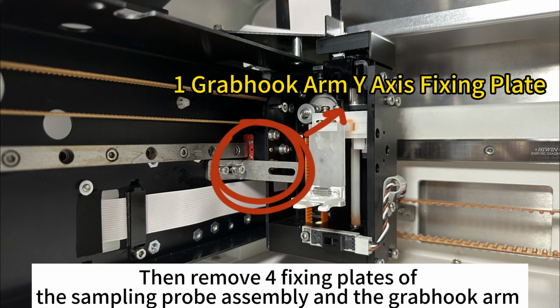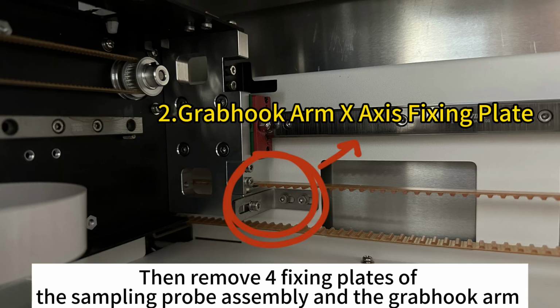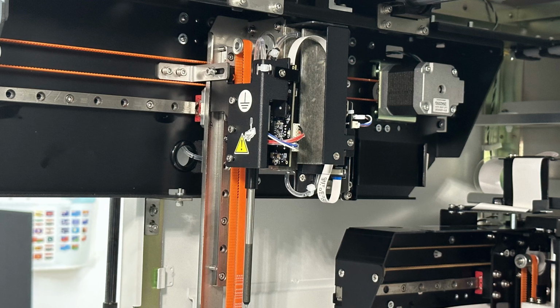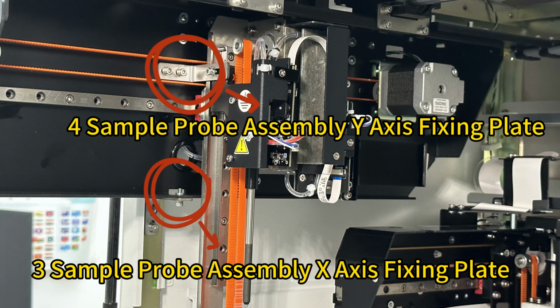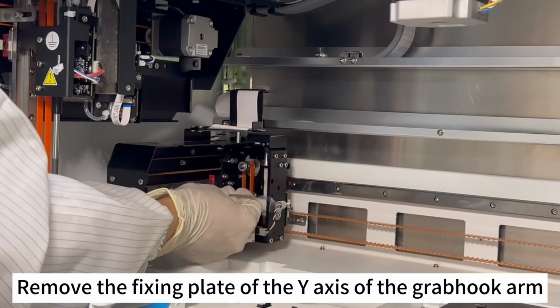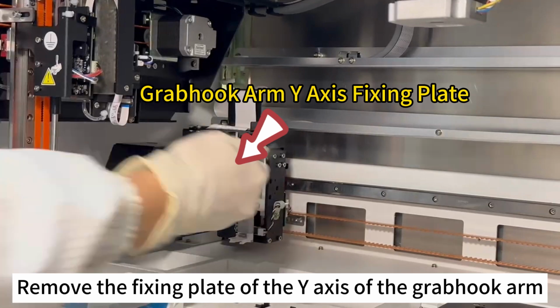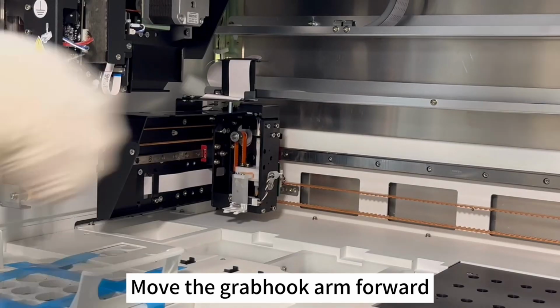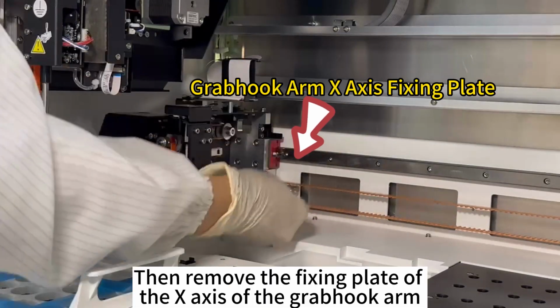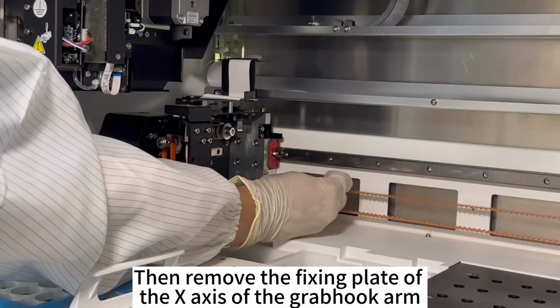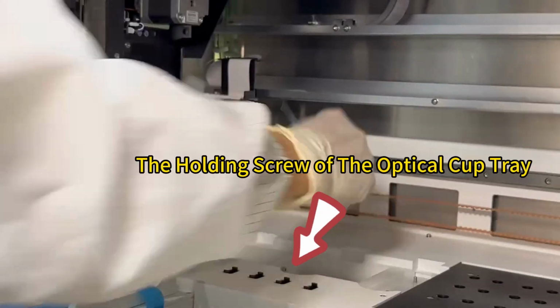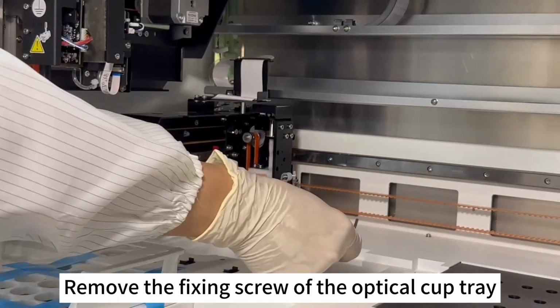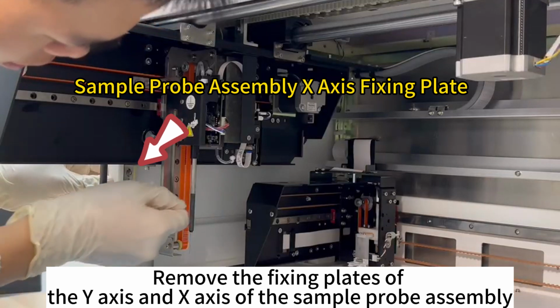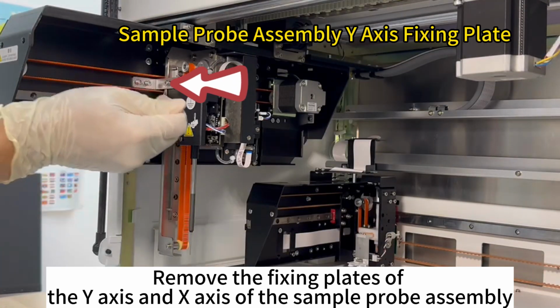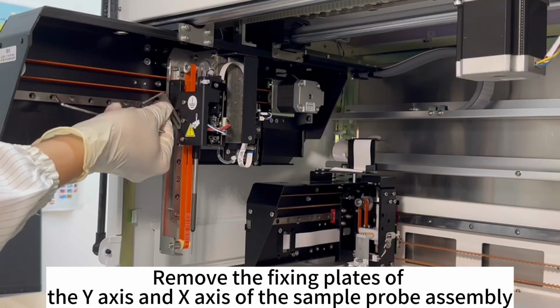Then remove the 4 fixing plates of the sampling probe assembly and the grab hook arm. Remove the fixing plate of the Y-axis of the grab hook arm. Move the grab hook arm forward, then remove the fixing plate of the X-axis of the grab hook arm. Remove the fixing screw of the optical cup tray. Remove the fixing plates of the Y-axis and X-axis of the sample probe assembly.